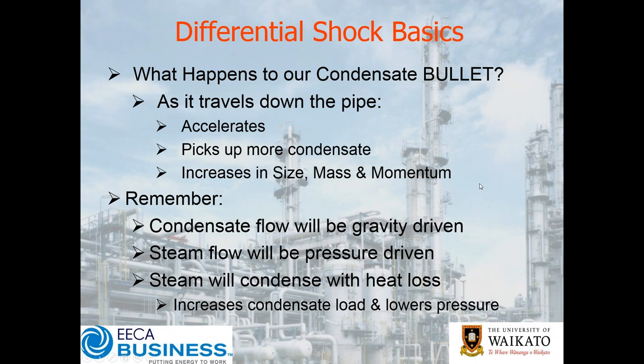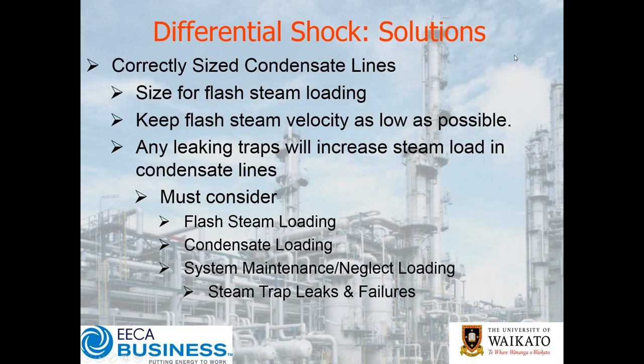So what do we need to remember? We want condensate to flow with gravity; steam is going to be pressure driven and will condense with heat loss. What's our solutions? One: correctly size our condensate line so our flash steam velocity in the line is low. We want our condensate loading low with a good drain so it's not building up in the line — a very small trickle of condensate in our line. If we have any leaking traps, that's going to cause a problem because we'll have extra steam — not just flash steam but live steam — coming into our condensate line, massively increasing steam velocity in the condensate line, which increases our wave height level, which increases the number of condensate bullets.